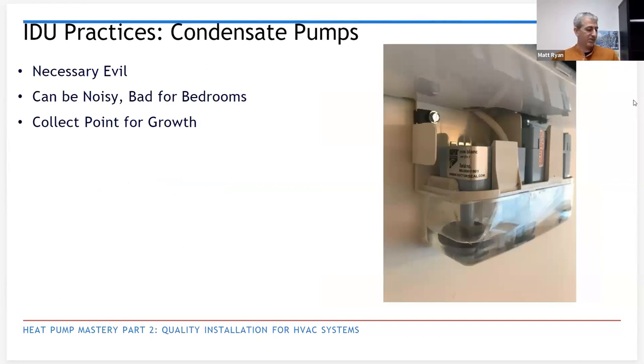This is condensate pumps. We try to keep it gravity wherever possible. Every once in a great while, you have to go to that condensate pump. Definitely not ideal for bedrooms. It's not a constant noise, it's sporadic, and if that thing cycles on in the middle of the night, it'll wake you up. They're not terrible, but it's definitely that noise in a silent night. It'll stick out to you there.